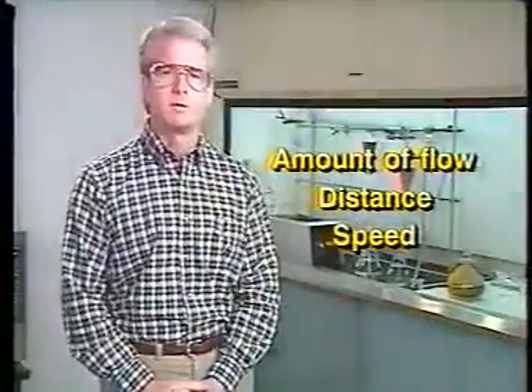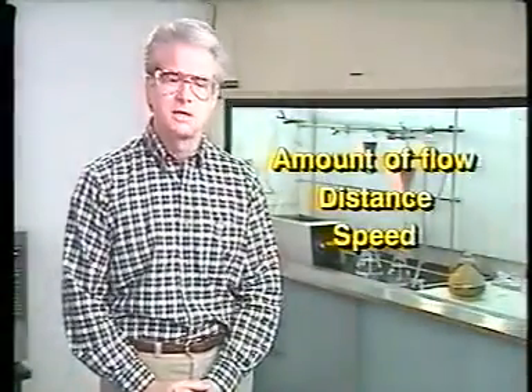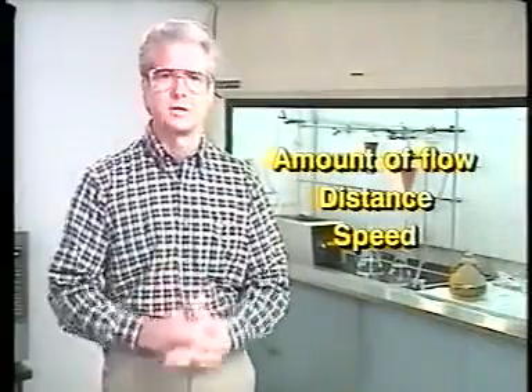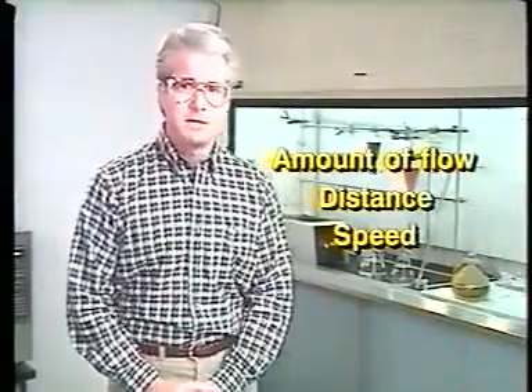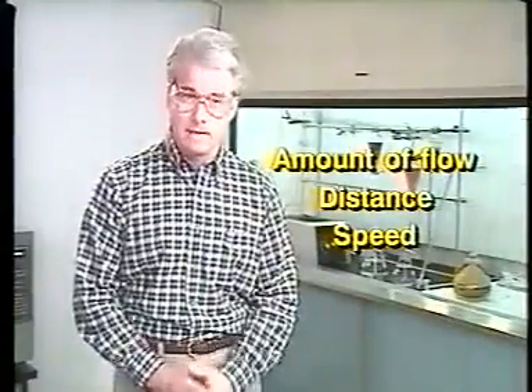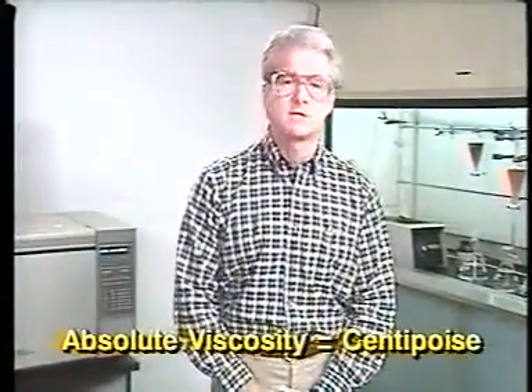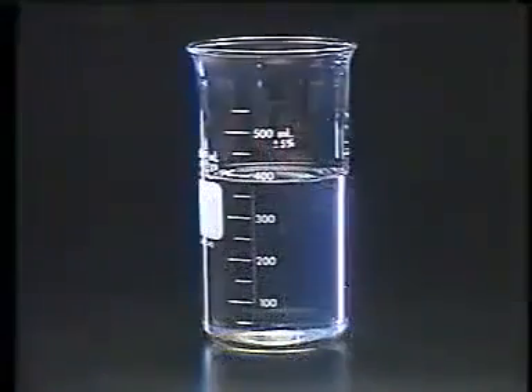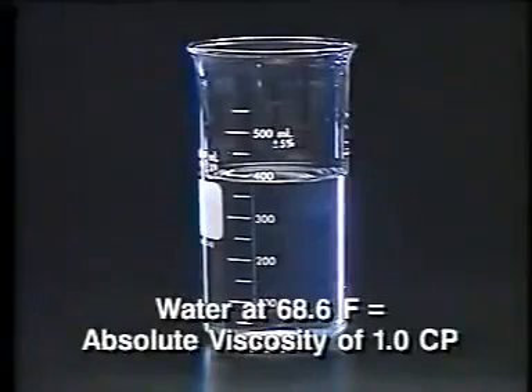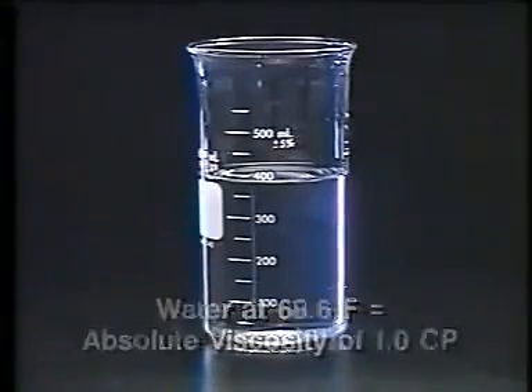In order to measure absolute viscosity, three factors must be considered: amount of flow, or the weight of the liquid, distance, how far it travels, and speed of flow, or how fast the liquid is. All three of these must be considered if different fluids are traveling through the same pipe under the same pressure. To do this, a new unit is needed. The unit that measures absolute or dynamic viscosity is the centipoise. As with other measurements, water represents the standard for viscosity. At 68.6 degrees Fahrenheit, the absolute viscosity of water is 1 centipoise.